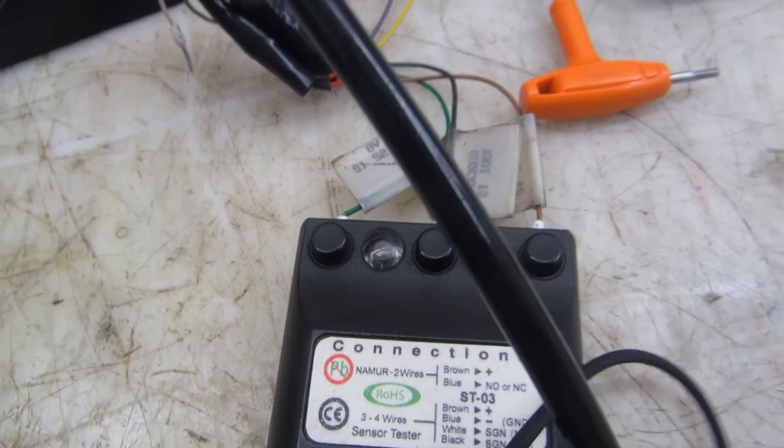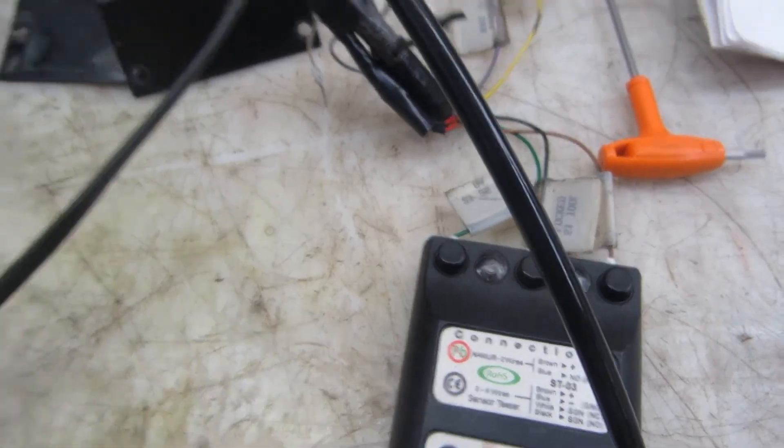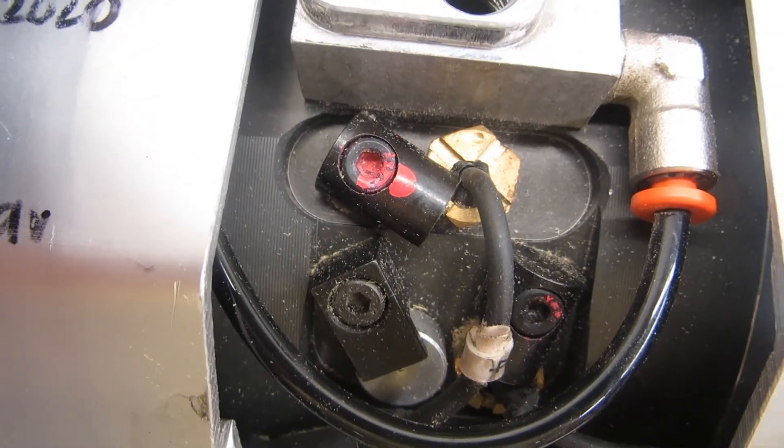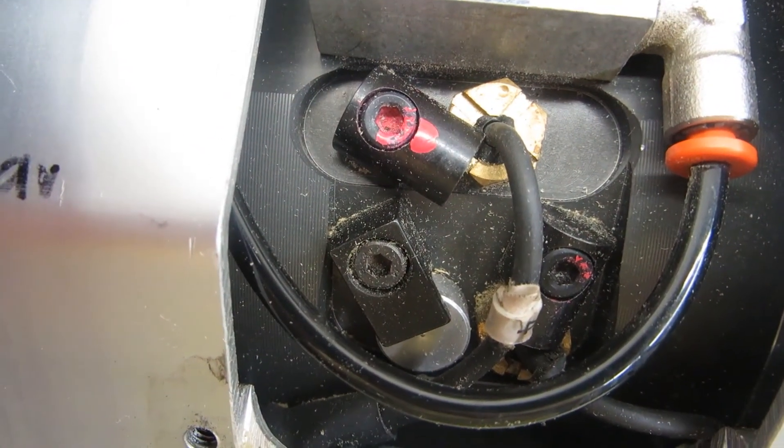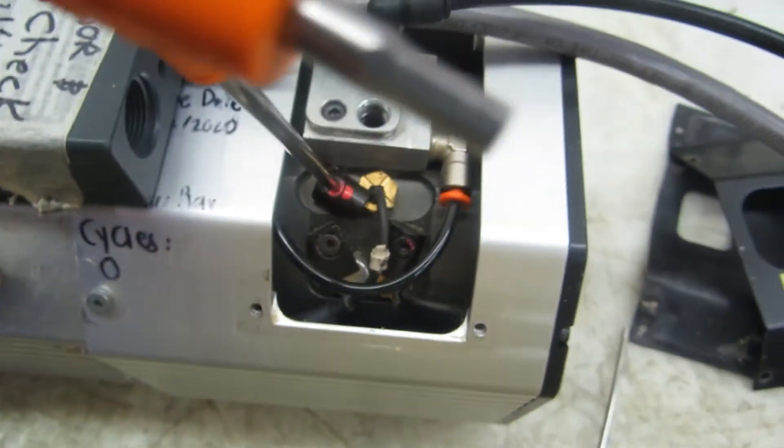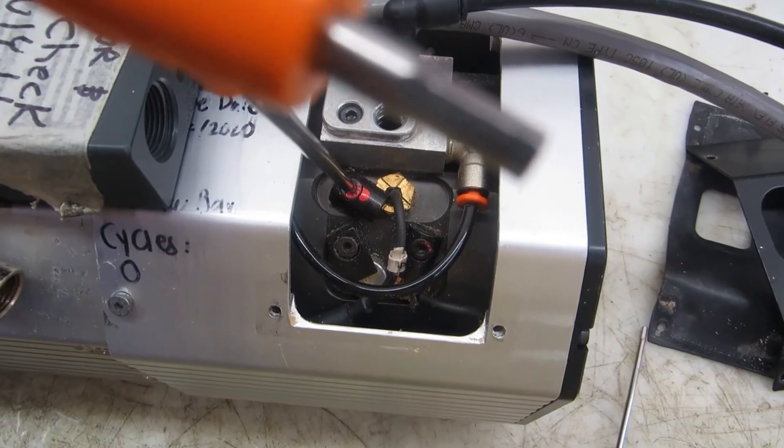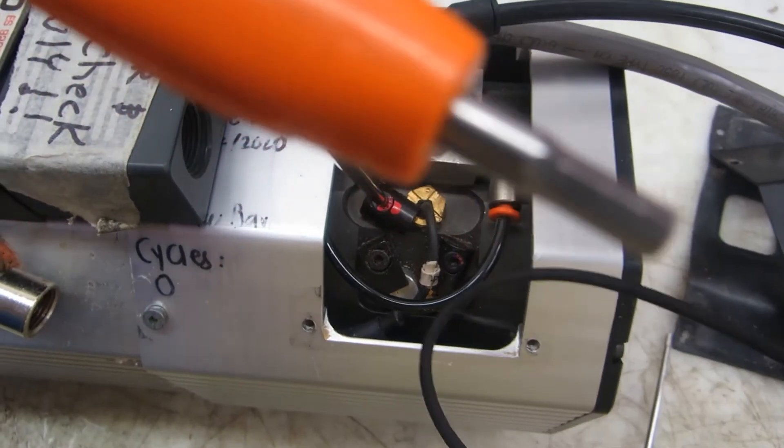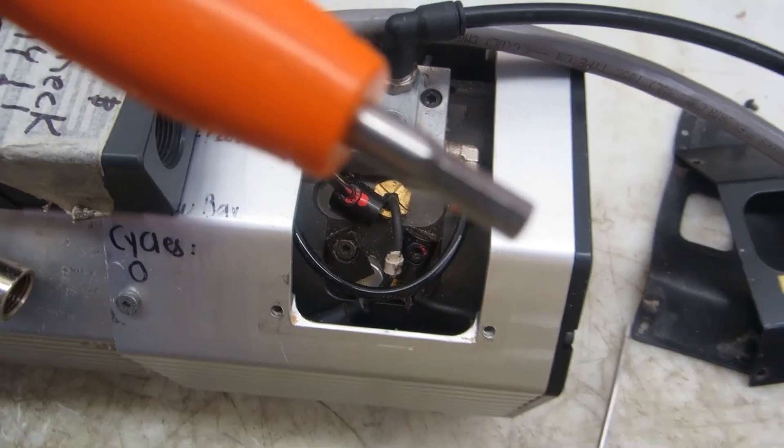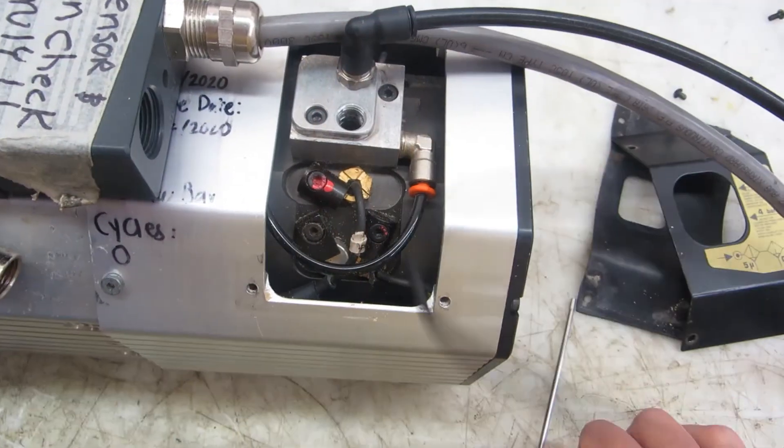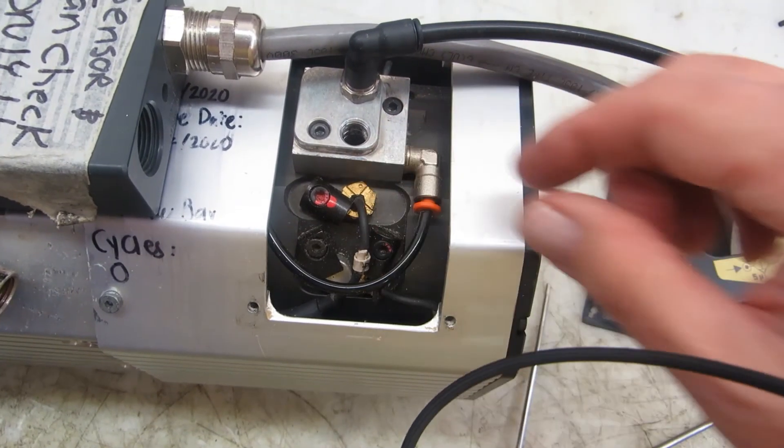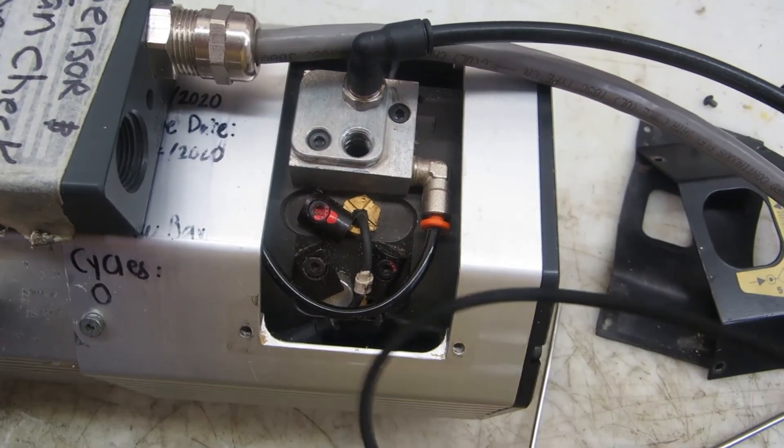If you have to adjust it and it's not set correctly, you have to go to S4 and adjust it first. You would use the three millimeter Allen wrench to adjust S4 first and then get that function and then go back to S1 and reset it. You would loosen it, then rotate the sensor to get the meter to come on and then lock it down.